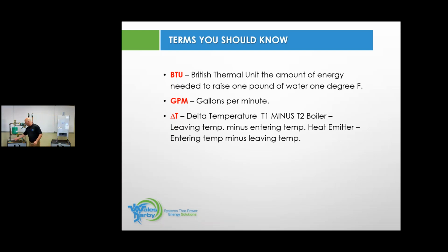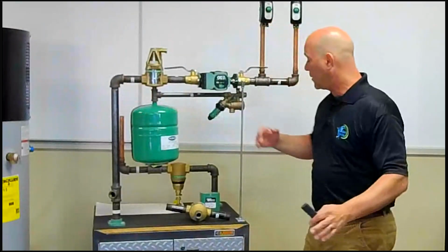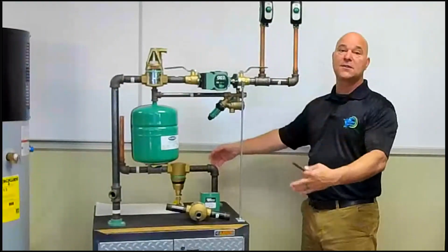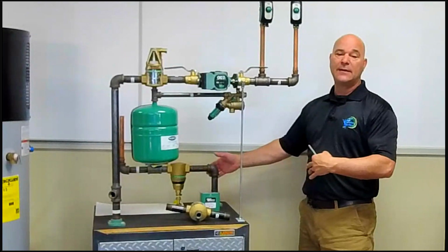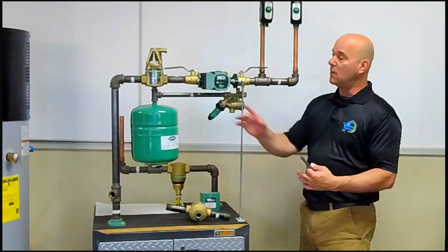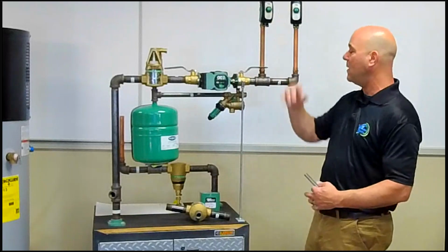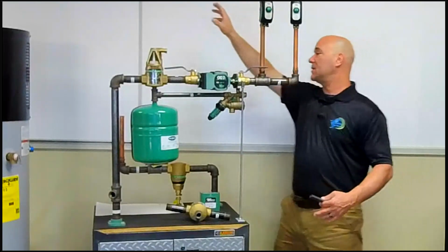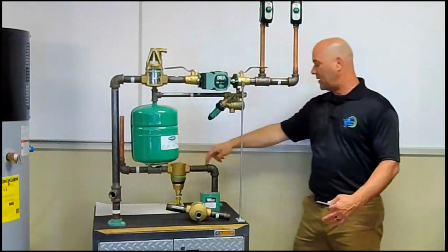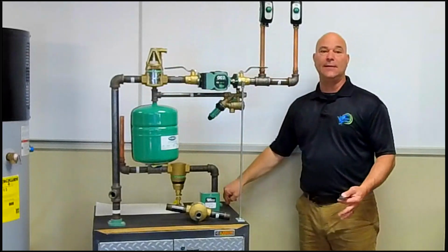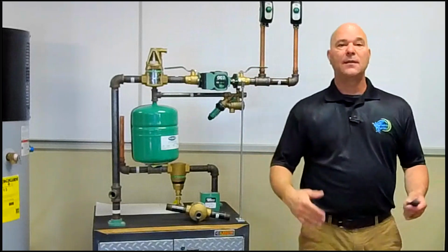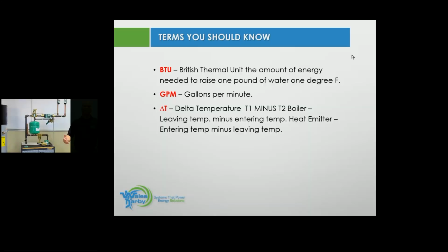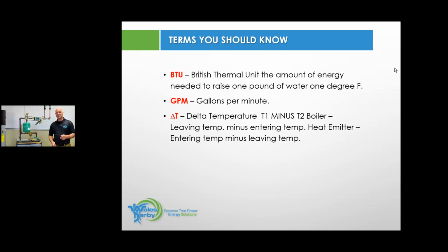But if this is my boiler and this is my supply header, and we'll use old term numbers, 180 degree supply, the goal is to go out through my heat emitters and come back on a design day at a 20 degree difference. So I would go out to my supply to heat my home. I would come through all of my heat emitters, come back down here to my return piping, go back into the boiler to be reheated. And the target number that we look for with cast iron is 20 degrees. We'll touch on that a little more.